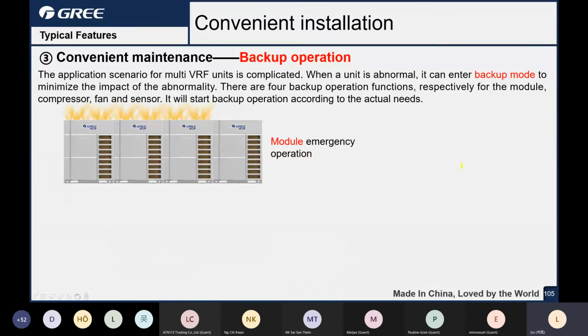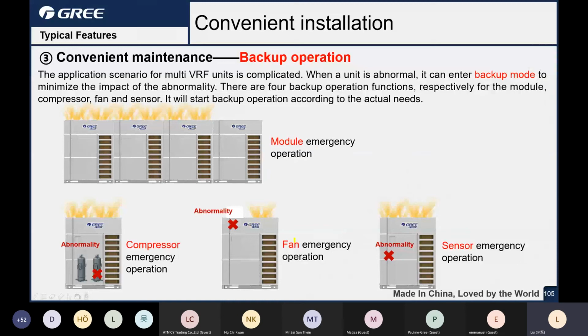Next one is the backup operation, such as the module emergency. That's the same with GMV5, and also the compressor emergency running backup and the fan emergency running. Another difference is that the GMV6 has sensor emergency. That's a new function. For example, if some sensor on the outdoor units is broken, the unit can use a very close location sensor as a backup, such as discharge and top shell. They can be backup, or the tube and ambient can be backup. Not the same detecting value, but if they use the backup, there is a correction logic for the parameter. But you know the backup is just the backup, just for emergency. Okay.